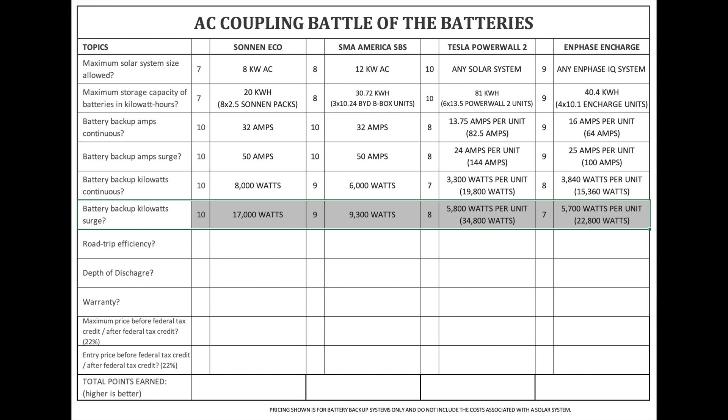Battery backup kilowatts surge. When you have a surge in amps, you also have a surge in power draw — these devices need the amps to start and require a spike in power to get going. They go hand in hand. So if you're looking to run a large appliance during a power outage, like an air conditioner, you need to look at the surge on these devices. The Sonnen Eco is 17,000 watts or 17 kilowatts. SMA America's SBS is 9,300 watts or 9.3 kilowatts. Tesla Powerwall 2 is 5,800 watts or 5.8 kilowatts per unit, or up to six connected together for 34,800 watts or 34.8 kilowatts. Enphase Encharge is 5,700 watts or 5.7 kilowatts per unit, up to four connected together for 22,800 watts or 22.8 kilowatts.